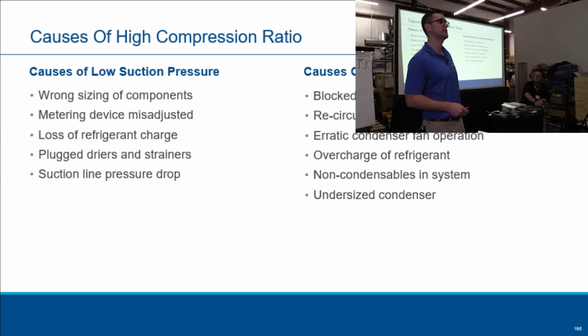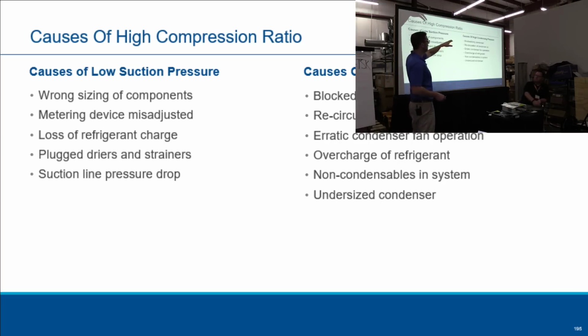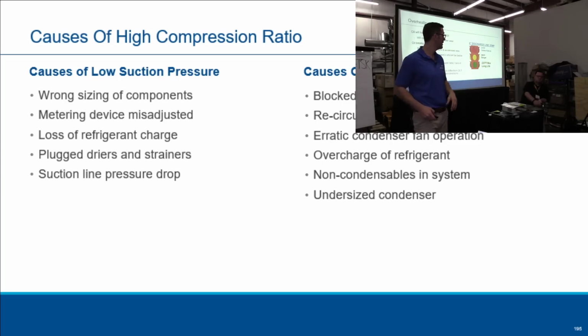High superheat. Exactly. Plug dryers. Loss of refrigerant for the low suction side. High blocked or dirty condenser for condensing pressure. Overcharge of refrigerant. Non-condensables in the system. Okay, here it is. This one is very important.